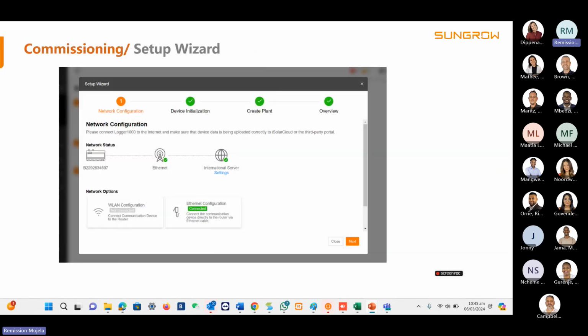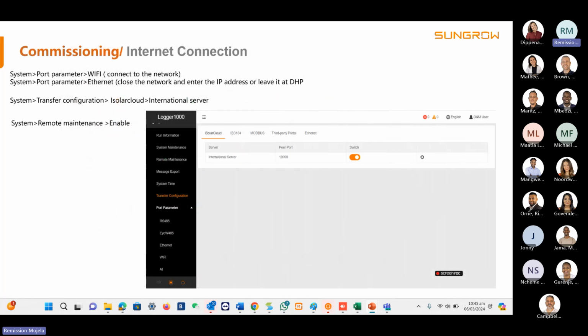Basically, it will take you from network configuration, device initialization, create a plant, and the overview after you're done. Then, just to make sure that all the settings are done correctly, the Wi-Fi connection is under port parameter, Wi-Fi or Ethernet, and then the transfer configuration under the server should be under this international server. And then if you create a plant, everything will be picked up.